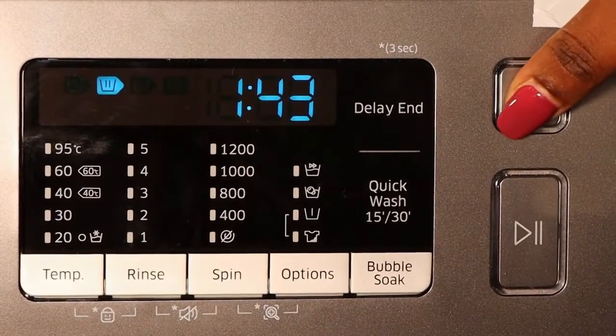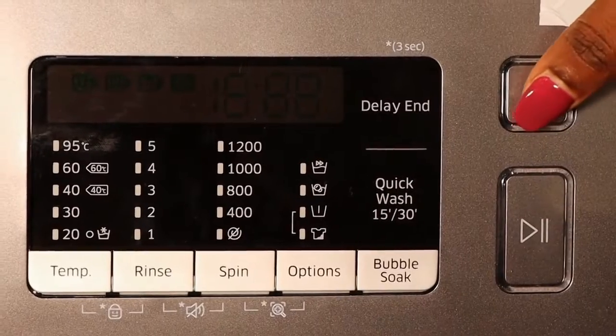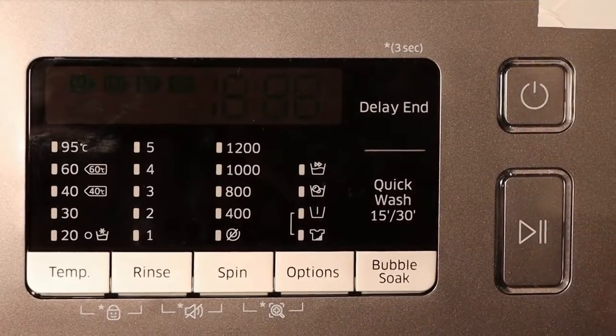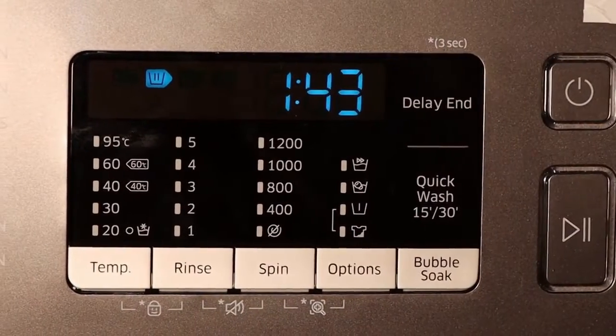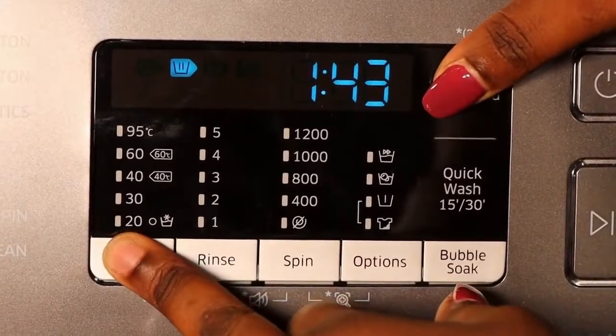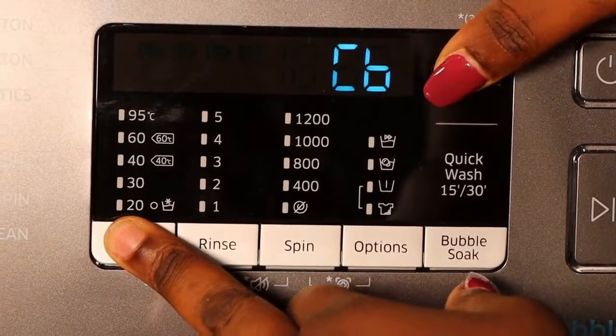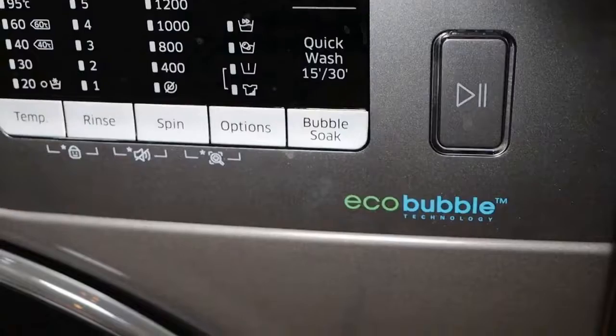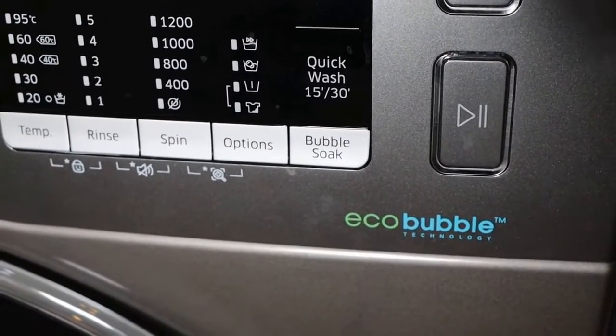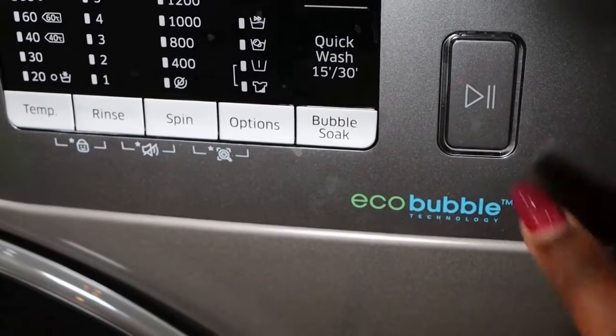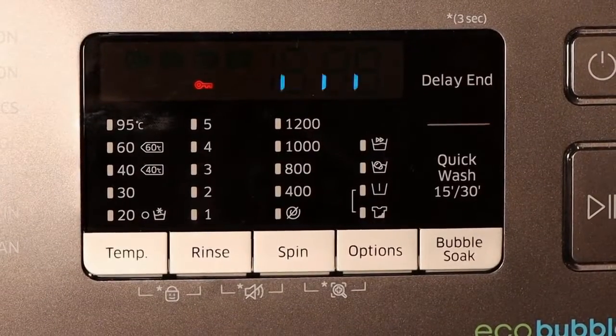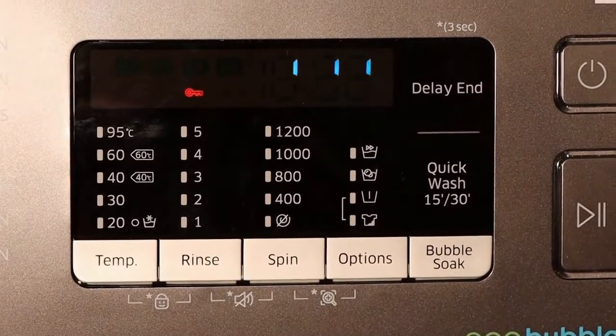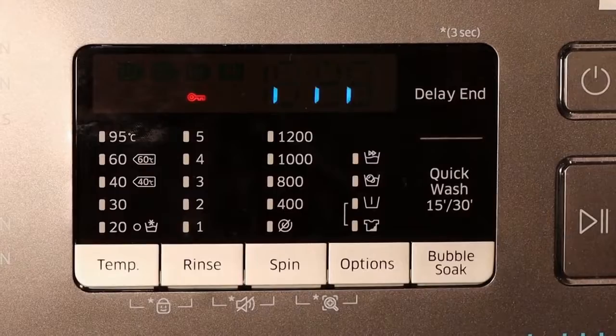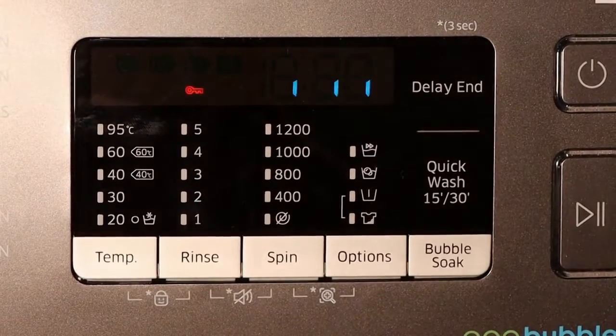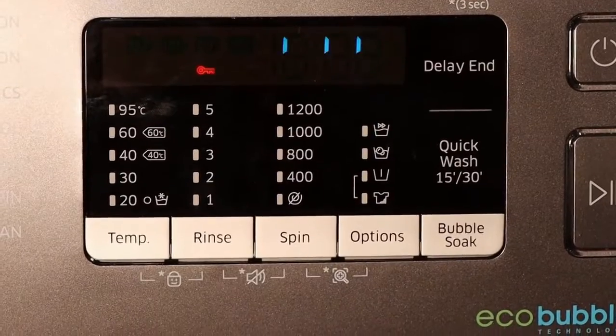So you switch off the power, then you switch on the power again. After that, you hold the temp and delay keys simultaneously for 3 seconds. After that, the machine enters the CB mode. You press the start-stop button. So you have to be patient. Let it just rotate clockwise and anti-clockwise, and it usually takes 3 minutes. Then after that, you will have calibrated your machine and your machine will be ready to use.